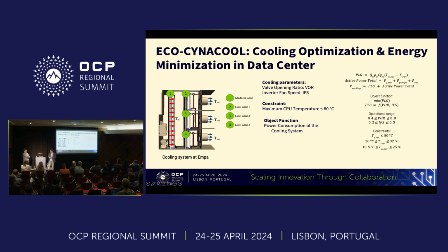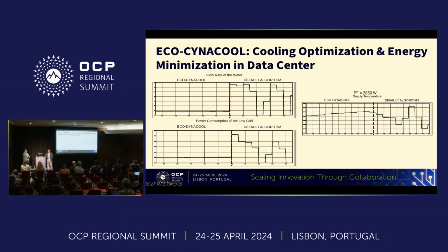Depending on these constraints, the cooling system's parameters are optimized. We compared the default and the current cooling system's behavior with the developed algorithm, ECO-Qube. The ECO-Qube can optimize the cooling parameters in a smooth way compared to the default algorithm, because the default algorithm can open and close the valves of the cooling system in order to set desired supply temperatures.